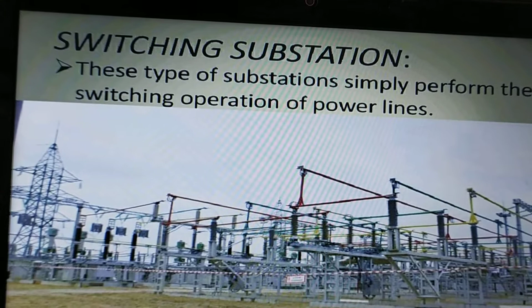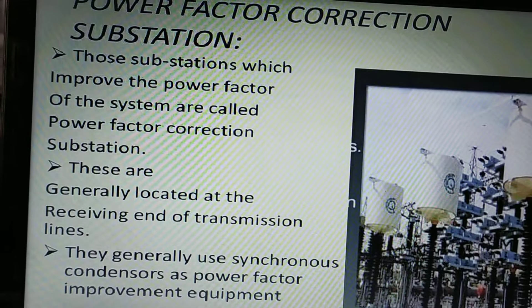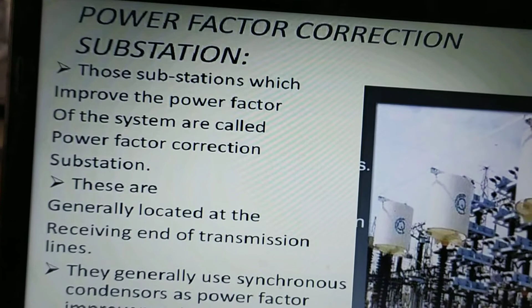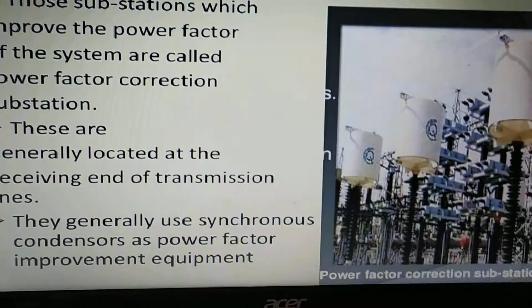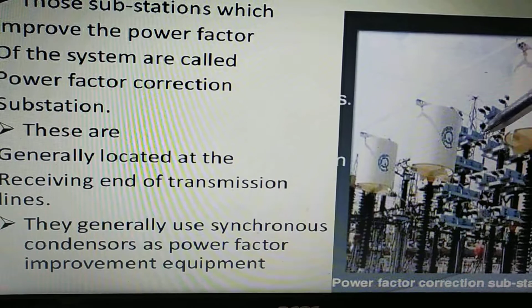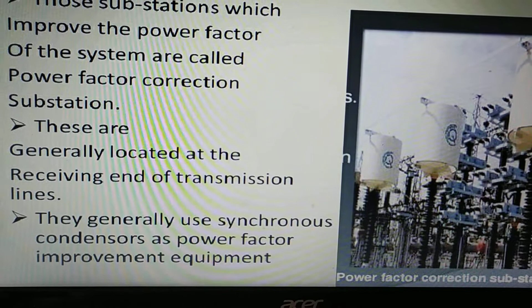Power factor correction substation. To improve the power factor of the power system, we should have a power factor correction system. Due to the parameters in the line, there is more variation in voltage as well as power factor, so there is a need to control the receiving end voltage and power factor of transmission lines. For this purpose, synchronous condensers are installed at the end of the receiving line. To accommodate the synchronous condensers, related equipment and accessories are required, and this type of substation is used at the receiving end of the line. In this figure you can see the synchronous condensers, used at the receiving end of the lines in order to improve the power factor.